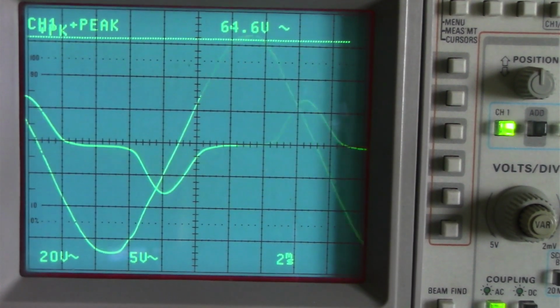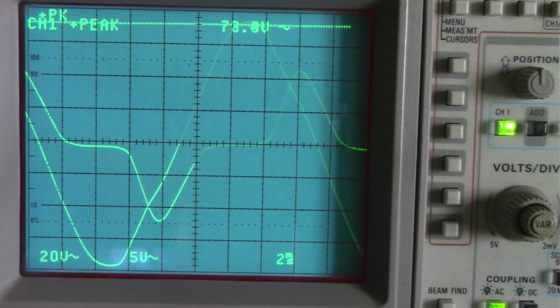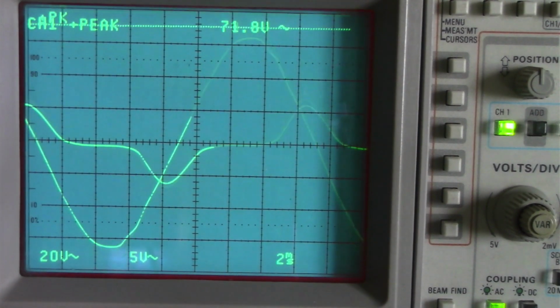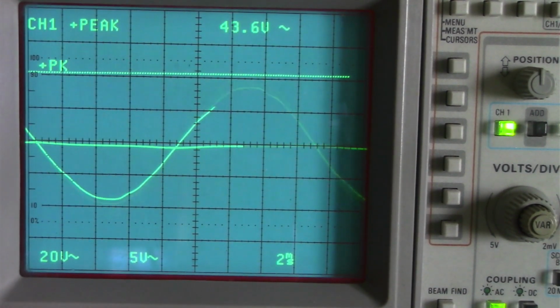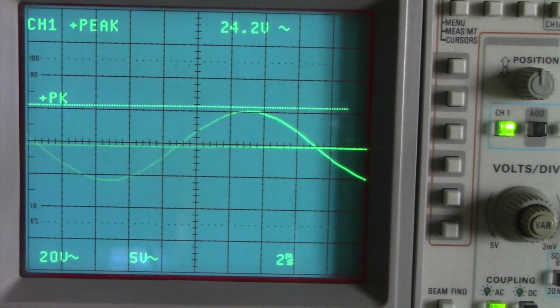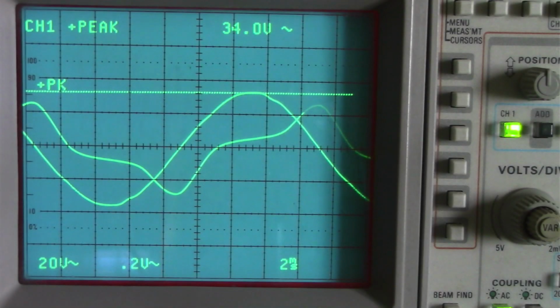We'll try for 80. I wouldn't want to stay here very long because we'll cook the transformer. And you can see that we had over 15 amps into that winding. At any rate, I think the point's been made that a transformer core will saturate when an excessive voltage is applied to any individual winding. It's safe to say that transformer simply would not survive under those conditions.